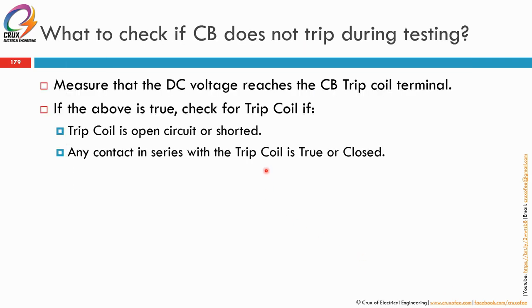So what to check if the circuit breaker does not trip during testing? Number one, you can measure whether the DC voltage reaches the CB trip coil terminal or not. Make sure you measure first whether the DC voltage reaches the CB trip coil terminal. If the DC circuit is okay, then you check on the coil itself. The trip coil may be open circuited or it may be shorted. If it is shorted, even though there's high current flowing through it, the coil is not enough to trigger the breaker to open. You can also check if there is any contact in series with the trip coil which is open or closed. Alright, so these are the troubleshooting steps. Looks pretty much straightforward. Checking from the top down, from the bottom up, to see where the circuit breaker trip coil continuity is disconnected.